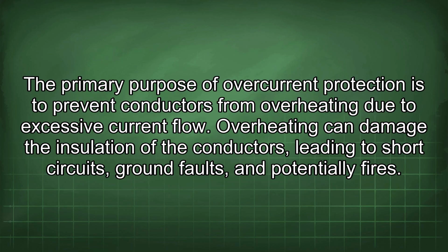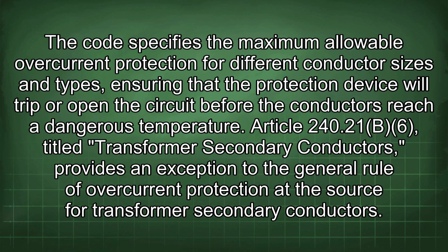The primary purpose of overcurrent protection is to prevent conductors from overheating due to excessive current flow. Overheating can damage the insulation of the conductors, leading to short circuits, ground faults, and potentially fires. The code specifies the maximum allowable overcurrent protection for different conductor sizes and types, ensuring that the protection device will trip or open the circuit before the conductors reach a dangerous temperature.